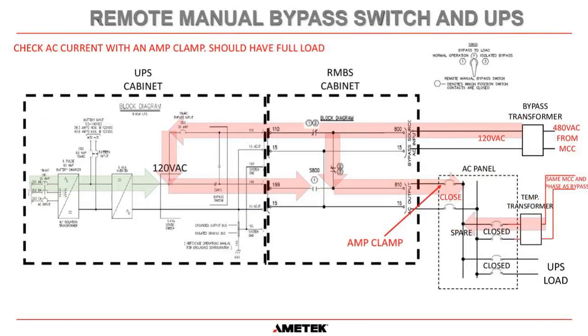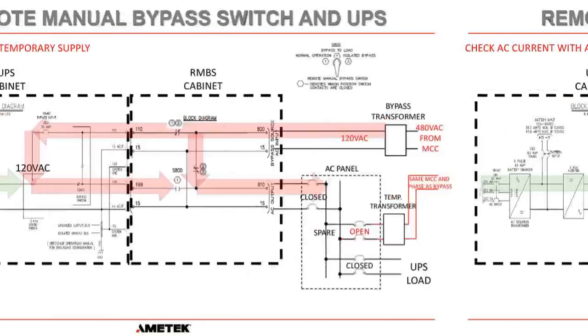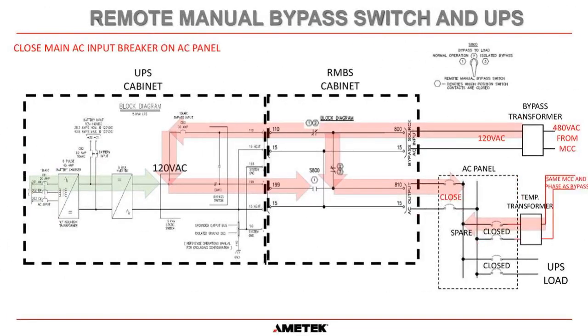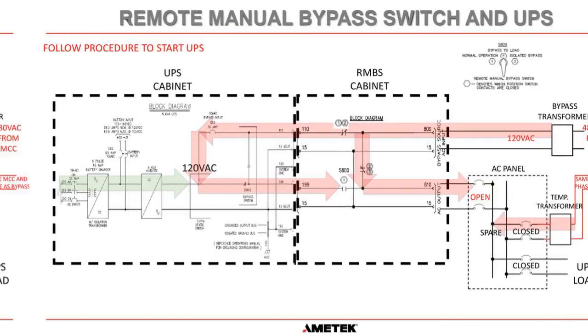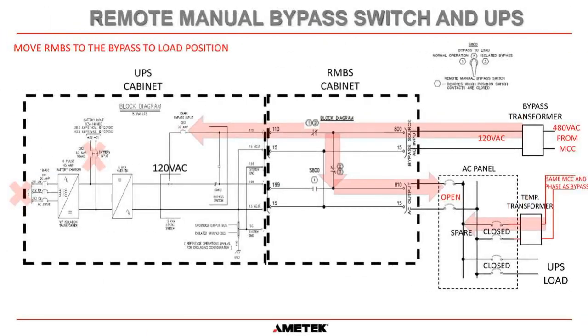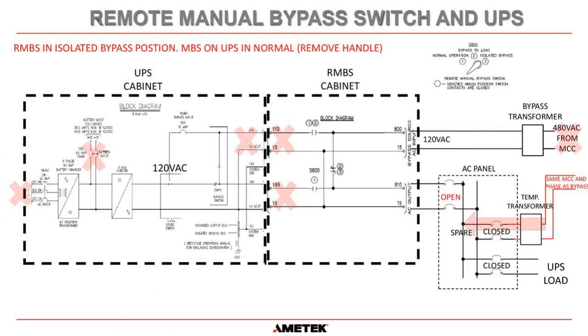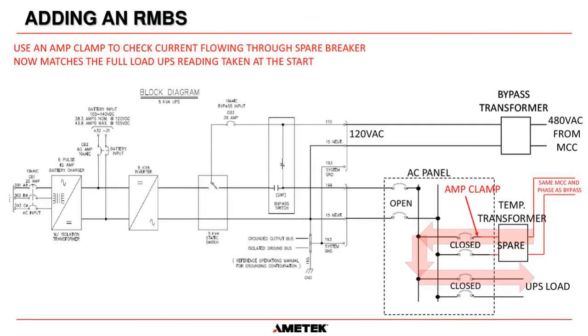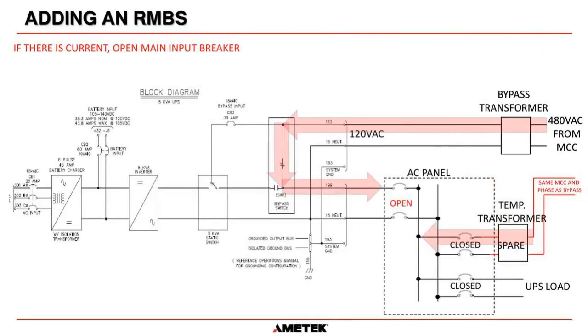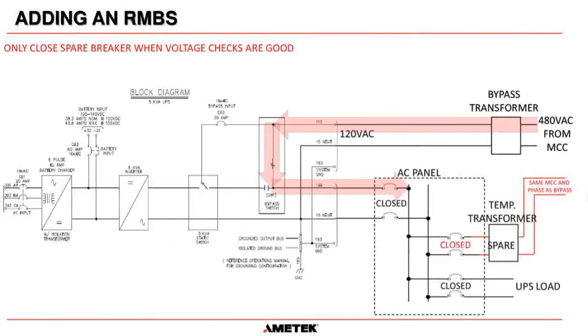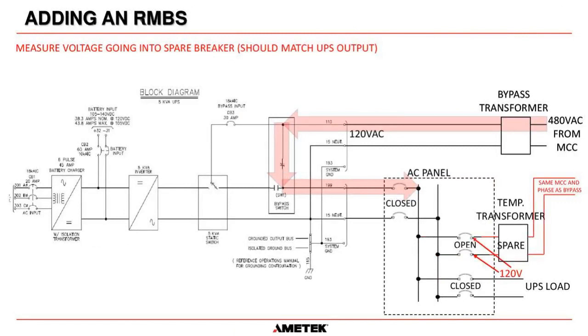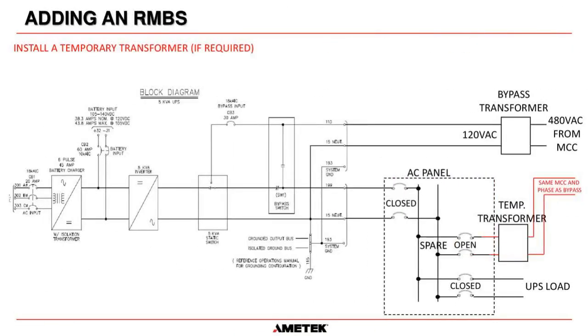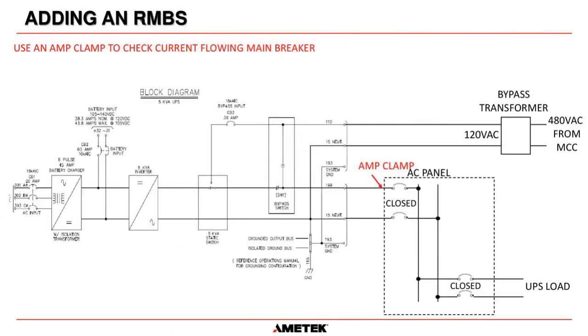Okay, another question we've been asked is, is an RMBS reliable? And the answer to that question is yes. The cam switch in those bypass switches are very reliable, but there is a caveat to that. The manufacturer recommends that they are exercised on a regular basis, basically at least once a year, because with all contacts in any switch, there is usually a wiping mechanism when you go from one position to another position that wipes the contacts clear of any oxidization or anything that could get onto those contacts. So they are very reliable, but I will say if I went up to any switch that hadn't been operated for 10 years, then I would be very dubious whether that switch is going to work correctly.